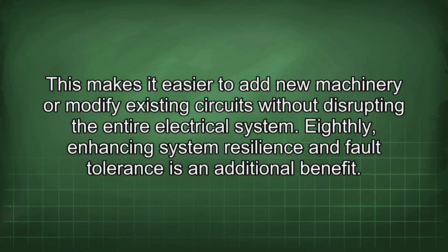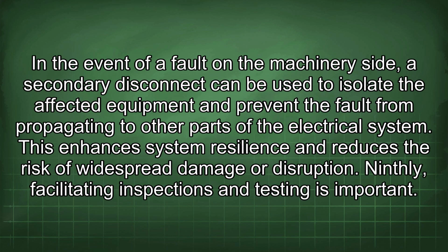Eighthly, enhancing system resilience and fault tolerance is an additional benefit. In the event of a fault on the machinery side, a secondary disconnect can be used to isolate the affected equipment and prevent the fault from propagating to other parts of the electrical system. This enhances system resilience and reduces the risk of widespread damage or disruption.